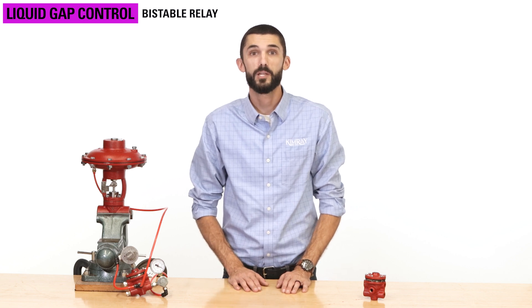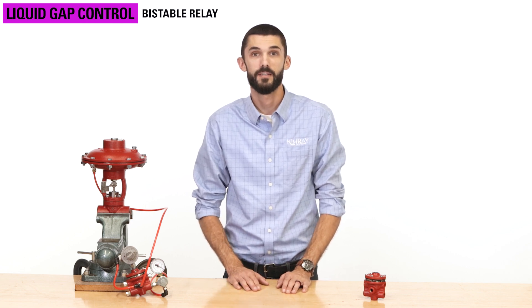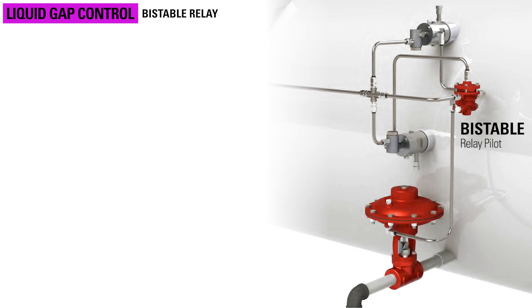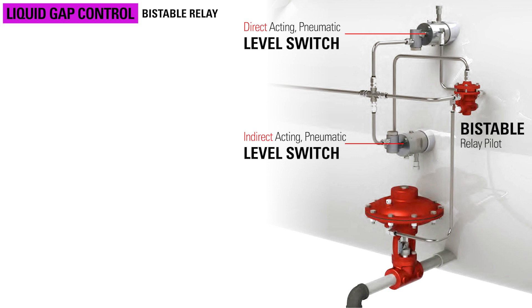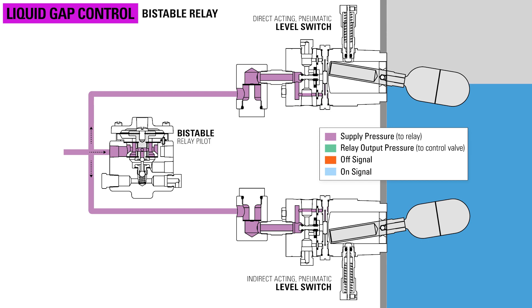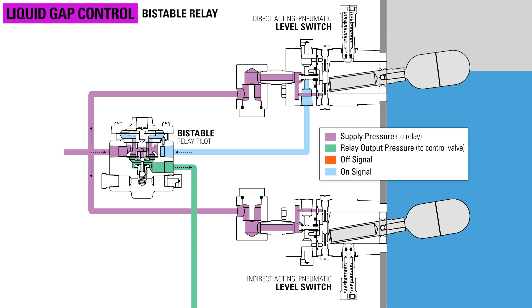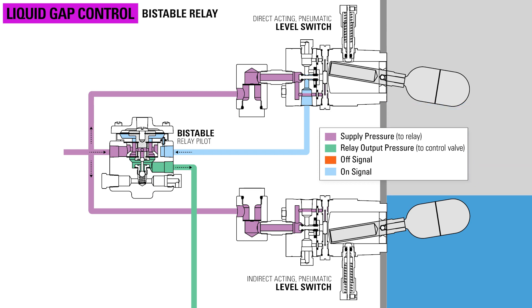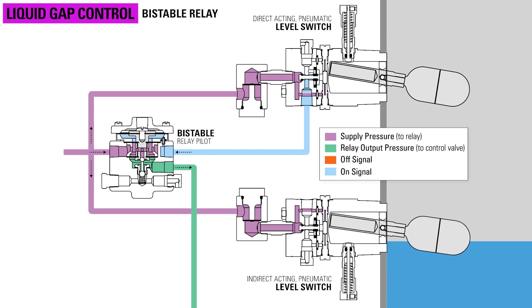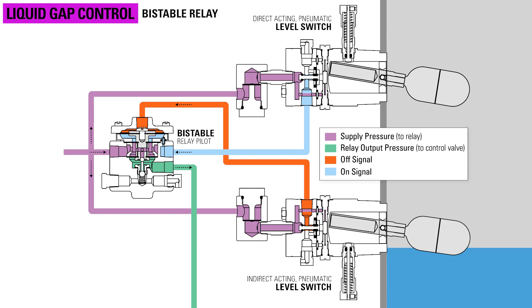You can also use the bistable pneumatic relay to help control a liquid level span. To do this you need a control valve and two level switches, one set to direct acting and one to indirect acting. As the float on the high level direct acting pneumatic liquid level switch moves upward, a pneumatic output to the lower side of the main diaphragm in the bistable relay is created. As the main diaphragm moves upward in the relay, the small ball on the pilot plug is unseated, allowing supply pressure to signal the control valve to open. As the liquid level lowers on the low level indirect acting liquid level switch, the float moves down, allowing the supply pressure to give a pneumatic off signal to the top of the bistable pilot. This overcomes the on signal and causes the control valve to close.